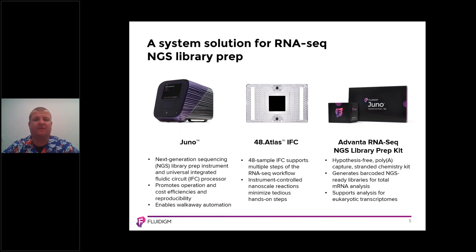Being an automated platform, the system only requires 30 minutes of hands-on time. The rest of the procedures are taken care of by the Juno system — things like the loading of the samples, the fragmentation of the samples, followed by the chemistry applications including reverse transcription, barcoding, and amplification, as well as the harvesting, i.e., the collection of the samples off of our microfluidic devices.